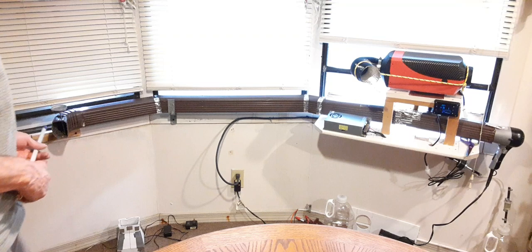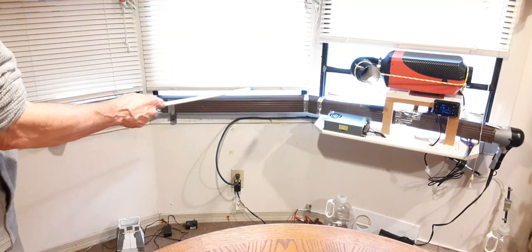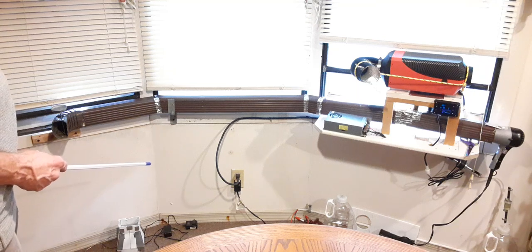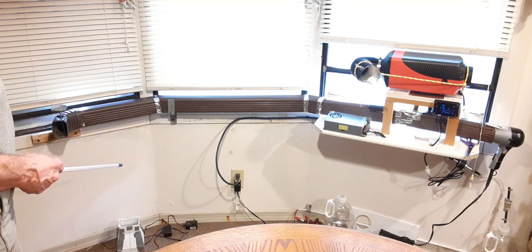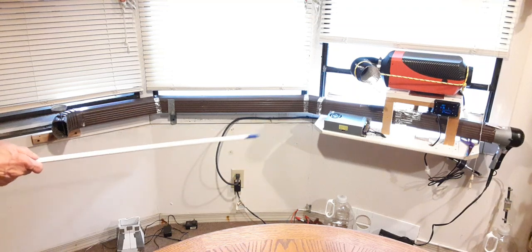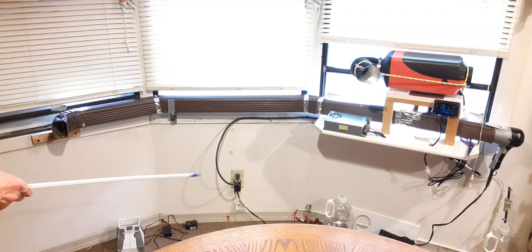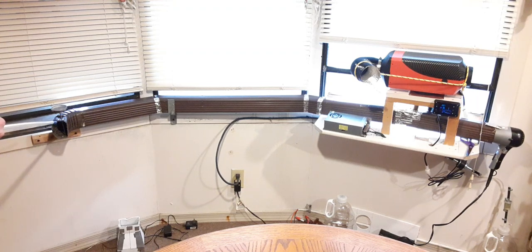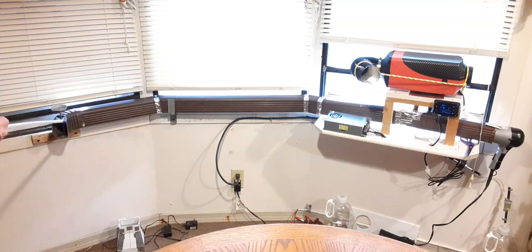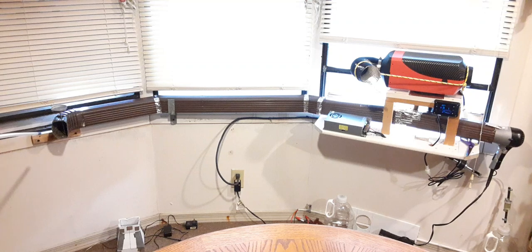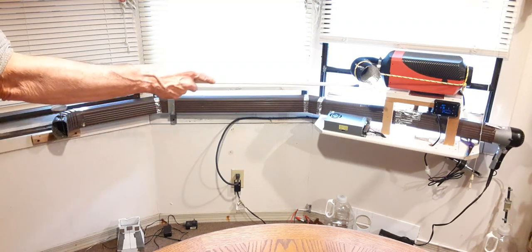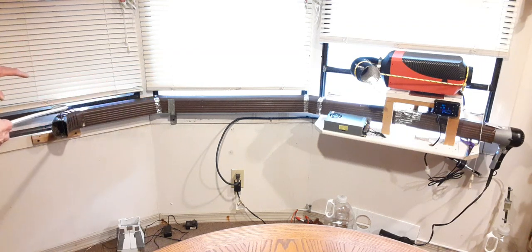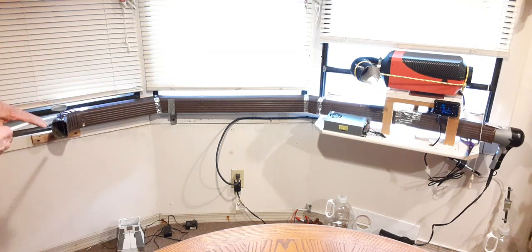What we got is about seven feet of duct run here, and that's quite a distance. Also, I want to point out I have an 85-degree elbow here, and that's a point of resistance. Unfortunately, it's not at a good place because it's at the weakest part of the airflow. The air has to come all the way through, and by that time it's losing its force, and then it has to bend and come out.